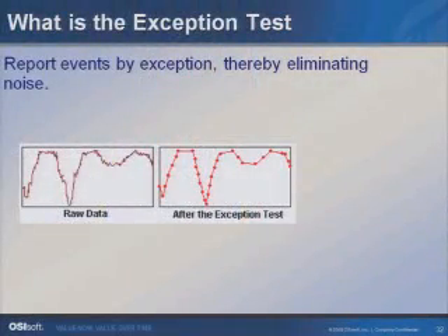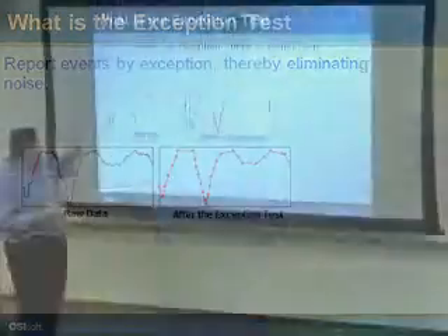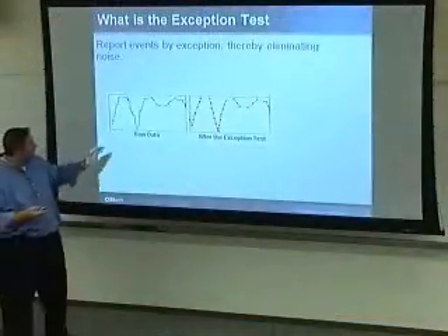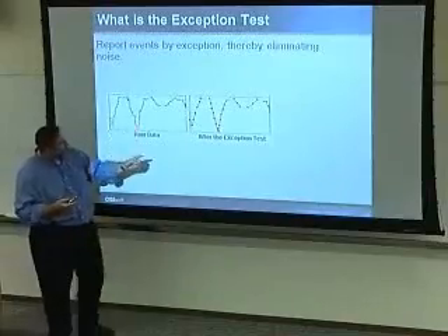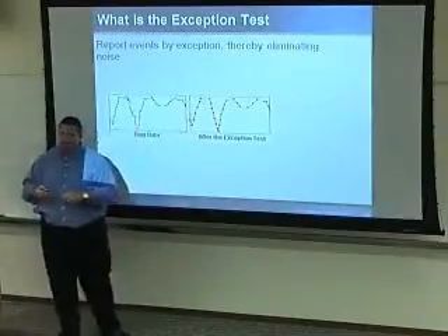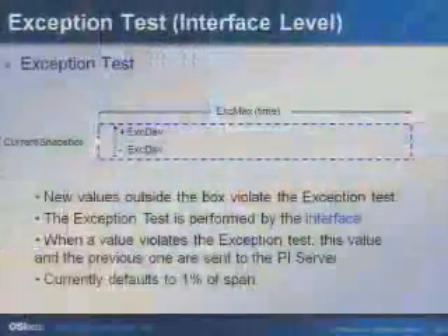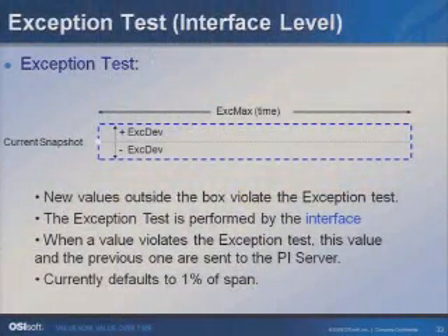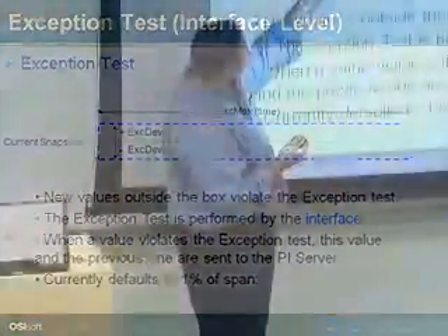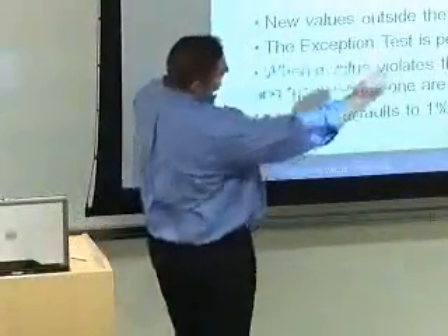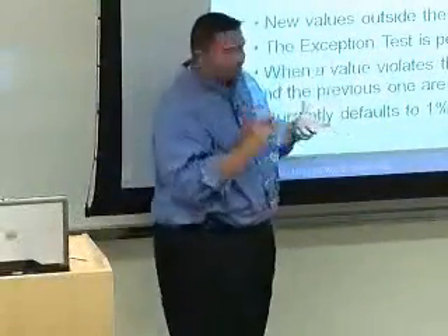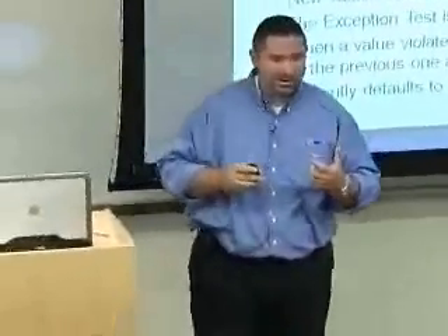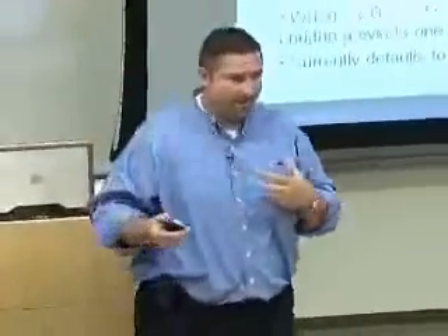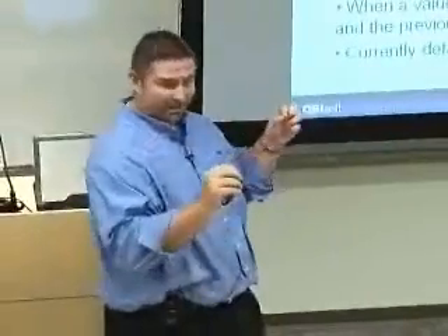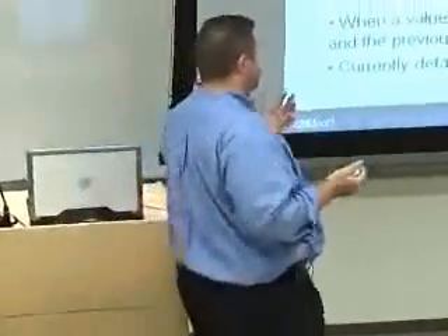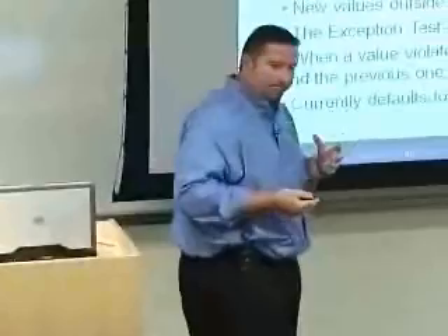So we'll talk a little bit here first about the exception test. Once events come into the interface, the raw data comes in - there's a whole lot of different points going in here - and after the exception test, you can filter out a lot of those. If we look at the exception test, we have this thing called an exception deviation and an exception max time. Basically, if something falls outside of this box, the interface will send that over to the server. You can make that nothing, so everything gets sent - it's completely configurable. By default, it's 1% of what we call a span.